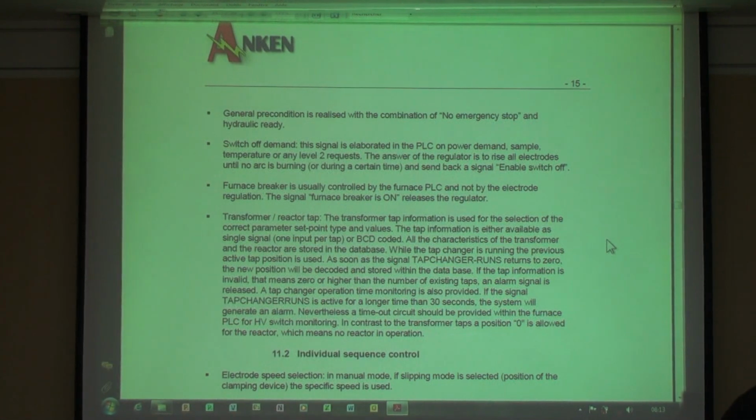그 스카다를 리셋하는 개념 같네. HV 스위치 리셋 개념 같아요. 모니터링 시간이 어느 정도 지나면 제로에서 다시 모니터링, 모든 게 원위치로 가는 거죠. 그러니까 리셋 개념이죠. 근데 운전반 설명할 때는 조금 틀리지. 이벤트가 시퀀스로 흘러갈 때 초창기 시퀀스로 되돌아가는 거예요. 그게 틀렸다는 얘기가 아니고 운전반에게 얘기할 때 포인트가, 리셋 개념보다는 탭 체인저가 잘못된 신호를 주고 있다는 식으로 얘기가 돼야 된다는 거죠. Understood?